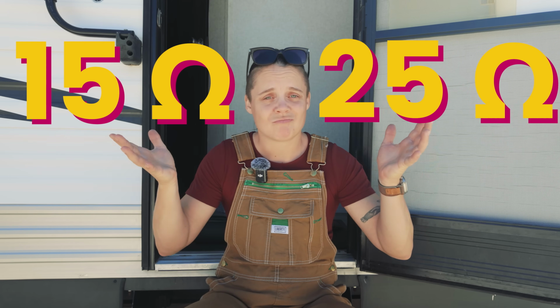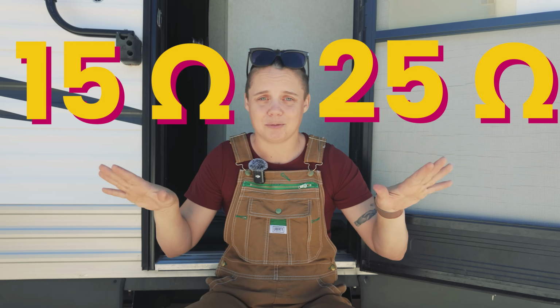If that reading is between this number and this number, your solenoid is probably fine and good to go. If you're getting a reading outside that range, you need to look at replacing your gas valves, because they're not opening up to let propane through.